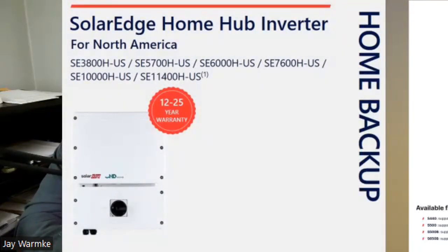And then the end phase, the SolarEdge inverters. These are fixed voltage inverters. Typically at the residential end, we're talking about single phase, so these are going to be 240 volt single phase. But their product line, primarily, you see it's a 3,800 watt string inverter, and that's really designed for 100 amp service with a 100 amp service panel. So that can be load side connected to your service panel and not exceed the 120% rule when hooking into that circuit breaker panel. So that's why that's kind of an odd number, but it all just matches out with the 100 amp on a 100 amp service.